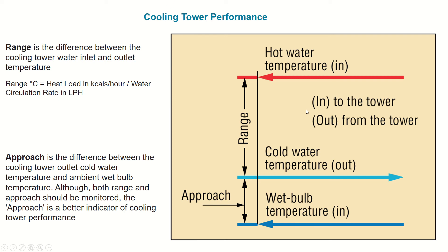In this lecture I will explain how to measure the performance of a cooling tower. The performance of a cooling tower is measured by two parameters which are called range and approach. The range is the difference between the cooling tower water inlet and outlet temperatures. The water entering the cooling tower is hot and the water leaving is cold, so the difference between these two temperatures is called range.